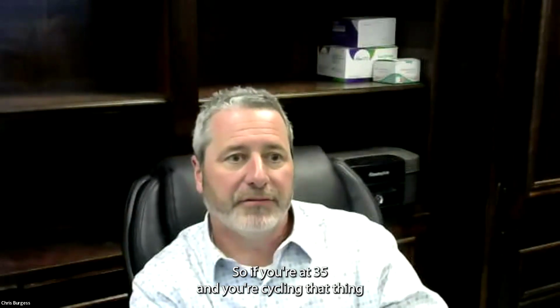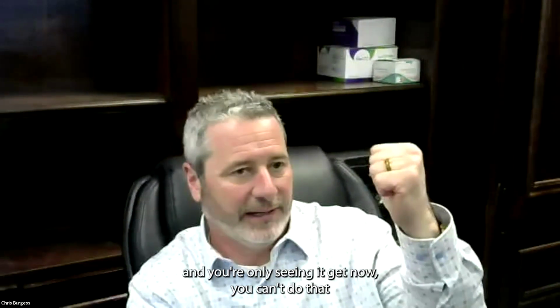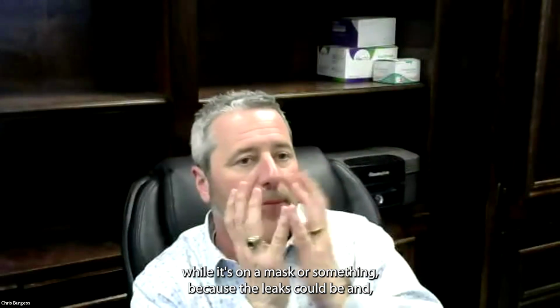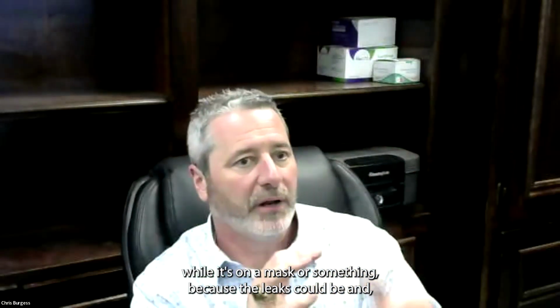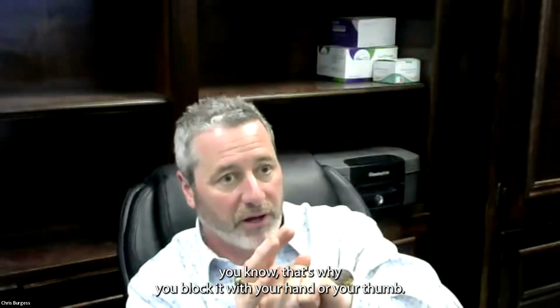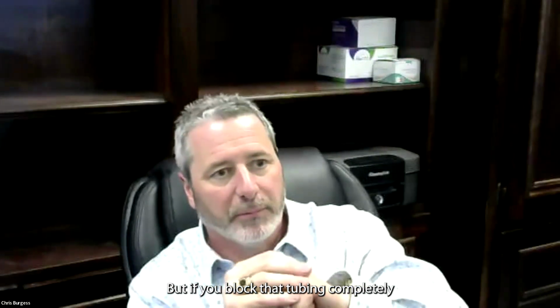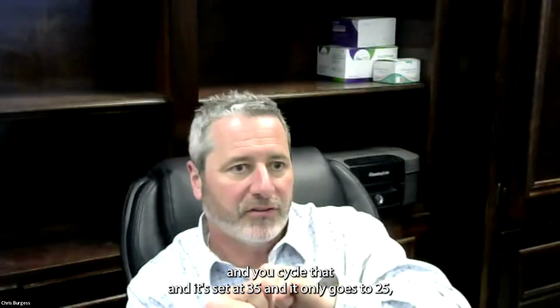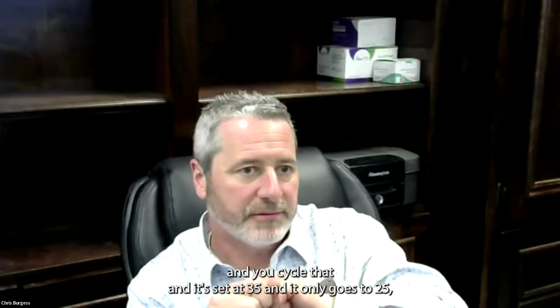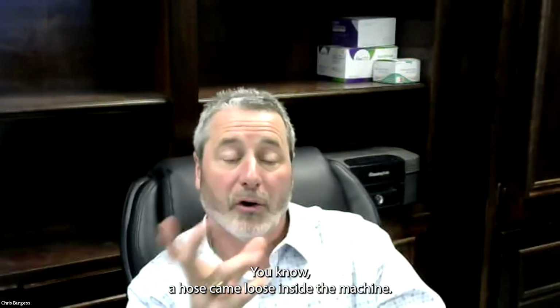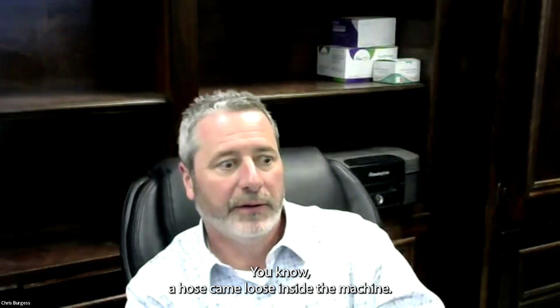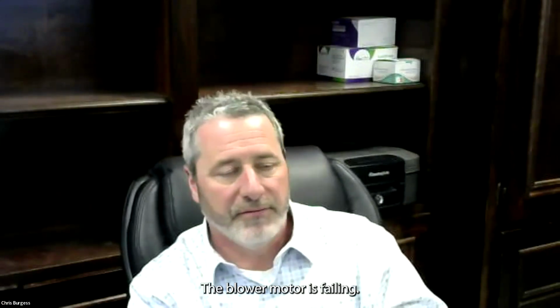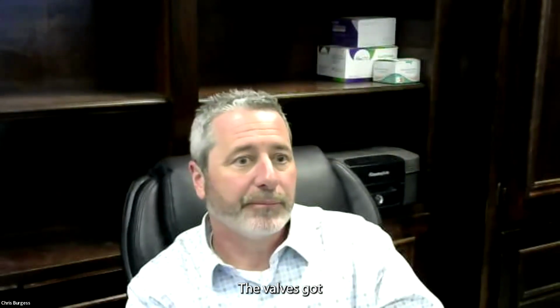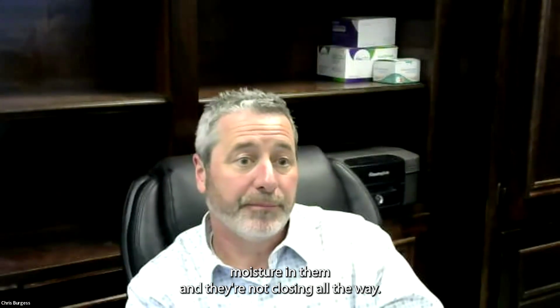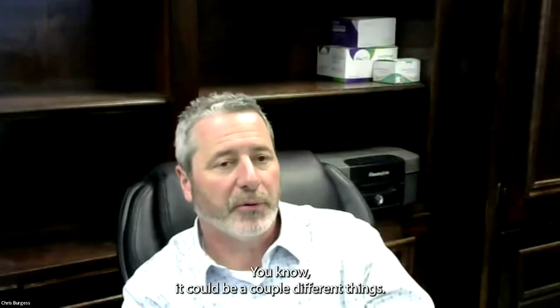So if you're at 35 and you're cycling that thing, you can't do that while it's on a mask or something, because of leaks, and that's why you block it with your hand or your thumb. But if you block that tubing completely and you cycle that and it's set at 35 and it only goes to 25, you've got a problem. Something's leaking, a hose came loose inside the machine, the blower motor's failing, or the valves got moisture in them and they're not closing all the way. It could be a couple different things.